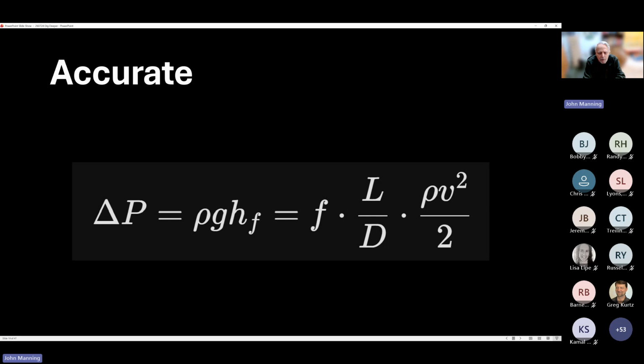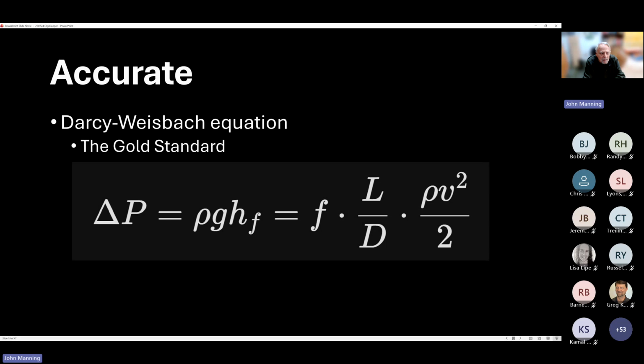In the area of accuracy, for those of you who may remember your fluid dynamics courses, this equation you may recognize, and it includes things like fluid density, the velocity squared, and a friction factor that incorporates things like Reynolds number and internal roughness factor of the type of pipe you're using. And you'll recognize this as the Darcy-Weisbach equation, considered to be the gold standard in trying to calculate pressure drops.